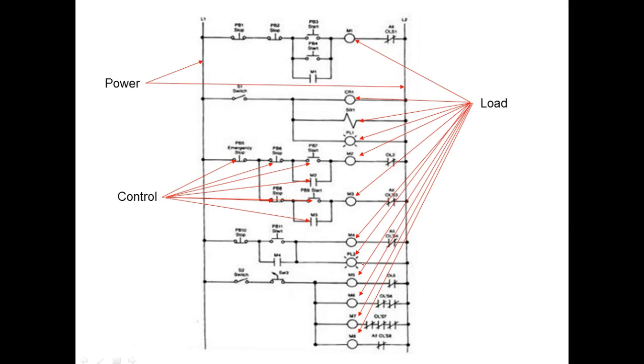The problem is these were dashpot timers, which work off a liquid. Now, what happens to most liquids when they get hot or cold? The viscosity changes. So when it turned winter, we'd have to go down there and adjust the timers, and when summer came, we'd have to go touch them up again, with the operator out there using a stopwatch to set it until it ran right.